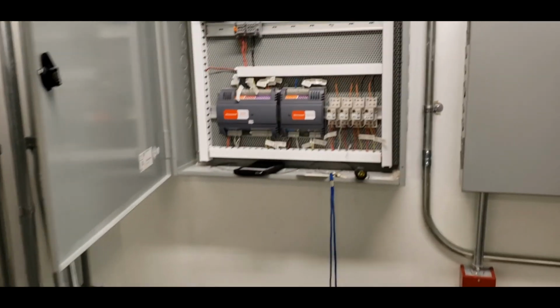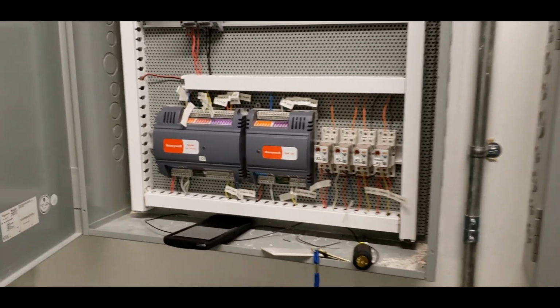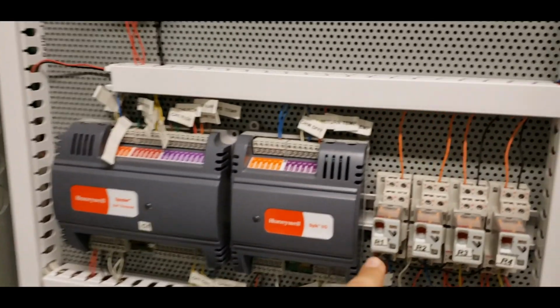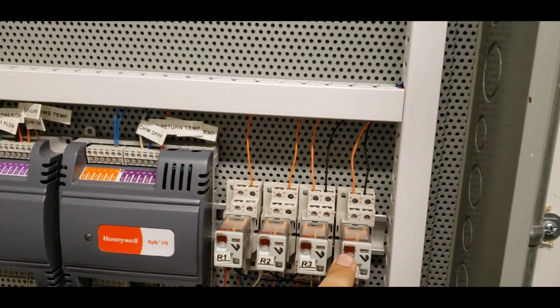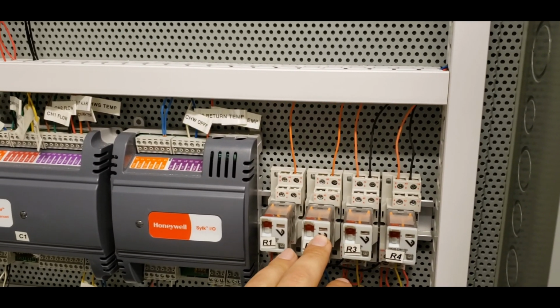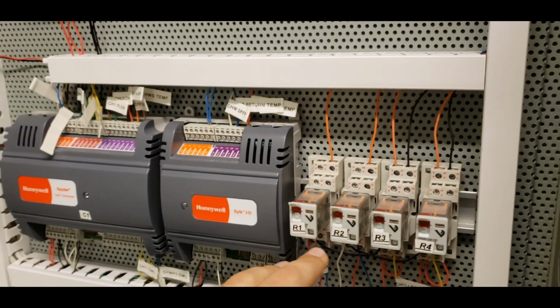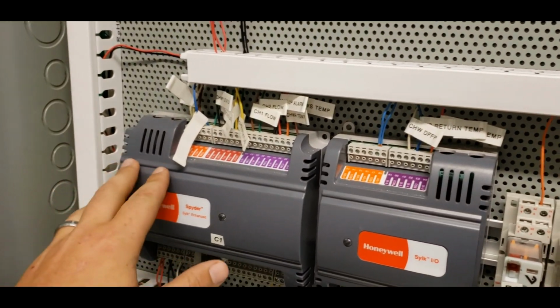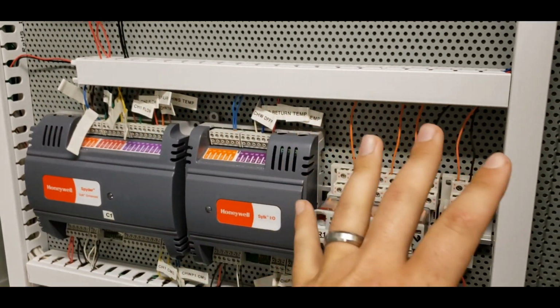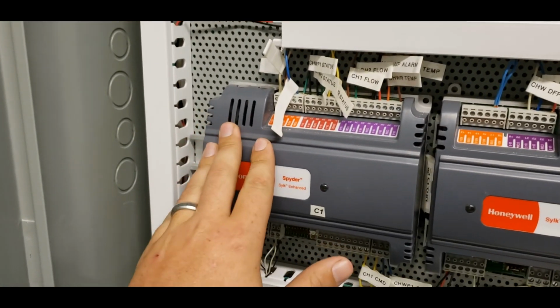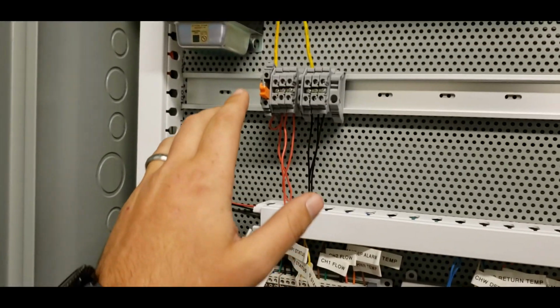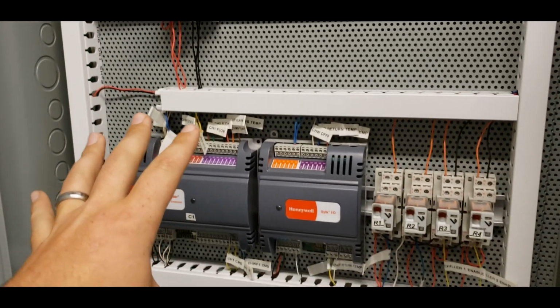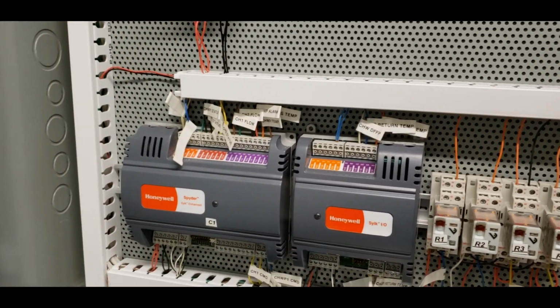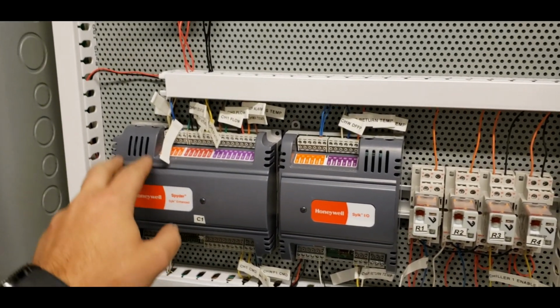Granted, the chillers were acting a little crazy because the pumps started coming in and out. So I've got overrides in all my relays, these are for my pump commands and chiller start stops. What I'm going to do is those overrides right here at the controller. What should happen is, giving these controllers off long enough, at least 60 seconds, I usually give them a few minutes.